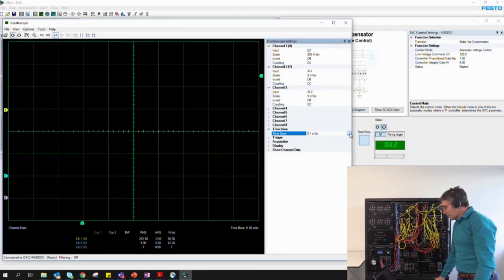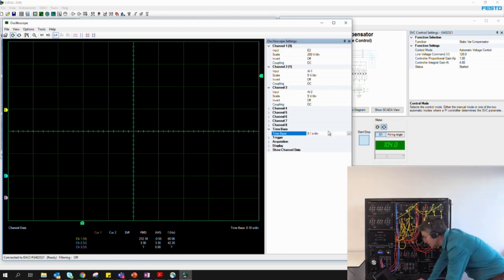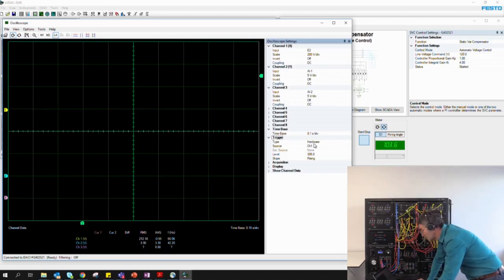To record this momentary event on the oscilloscope, I set the time base to 0.1 second per division, which I know will yield good results. I set my trigger type to hardware, telling the oscilloscope to wait for a specific hardware event to start recording. I will wait for this event on channel 1, which is my E2 voltage, the receiving voltage, and I set the trigger level at 305 volts. 305 volts is just above the peak voltage on my line voltage, and I know I will get the peak voltage when I change the load, which is the moment I want to record the data.